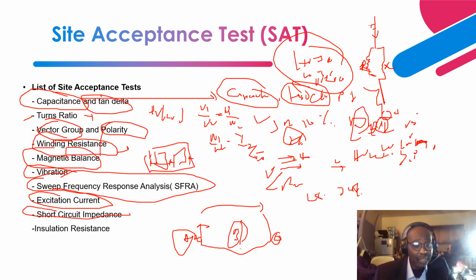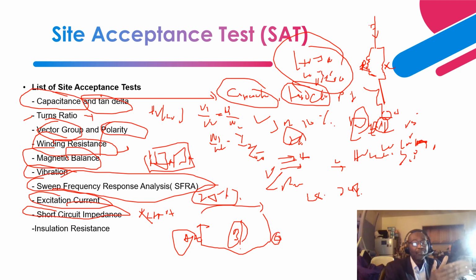Next is short circuit impedance, right? Okay, so that is your leakage impedance plus your resistance, then you calculate your Z, right? So you compare this testing with what is performed in the factory during the factory acceptance testing. The goal is to make sure that there's no deviation beyond 7.5%, right? That is the deviation. So you always compare the testing results with what was performed earlier on, or what was performed in the factory during the factory acceptance testing.